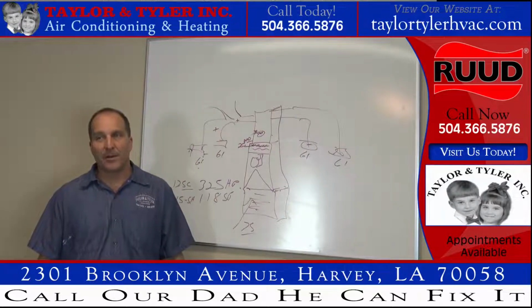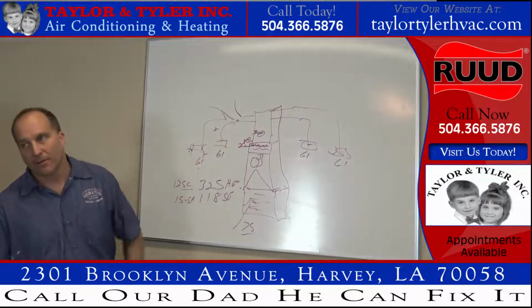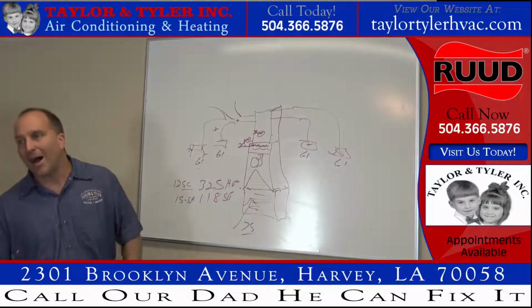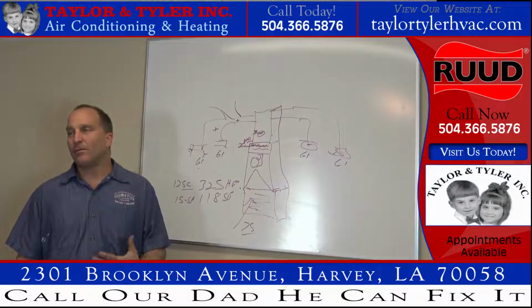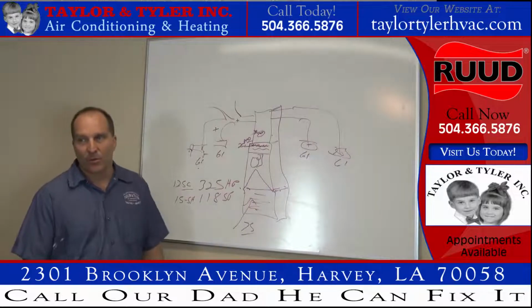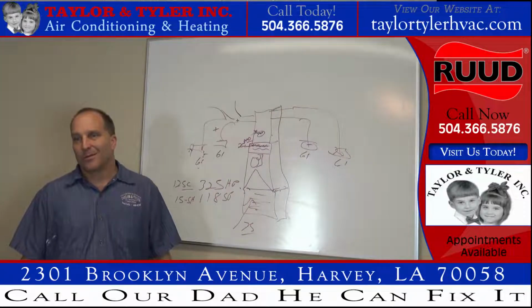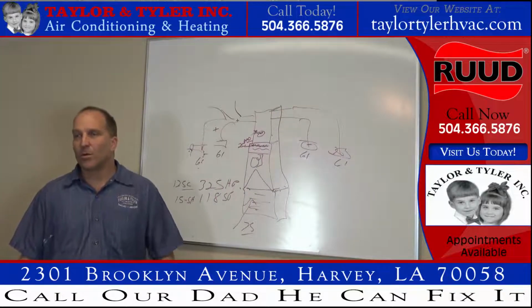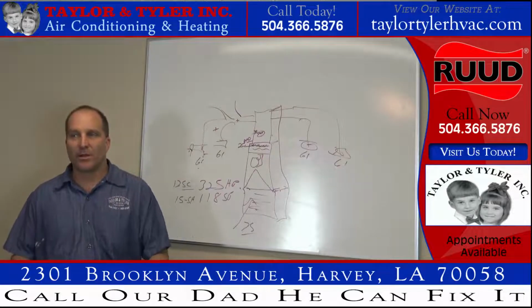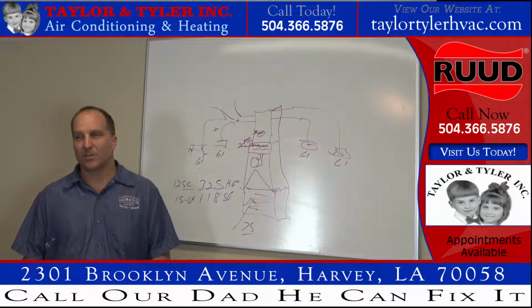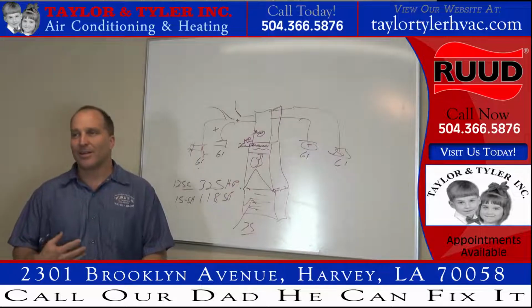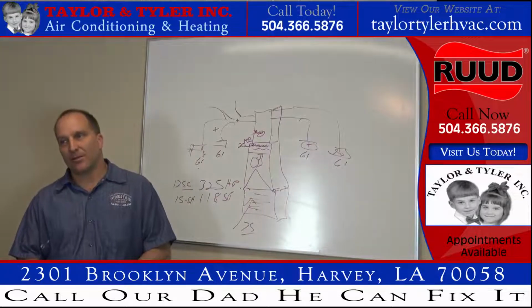But if you're telling me, well, my superheat's off, my superheat's too high, it's running 24 and it's supposed to be running 12, well, tell me why. What's going on? Give me more details. Look at this system, see how it's installed, all this kind of stuff. I can only diagnose with the answers that you give me.